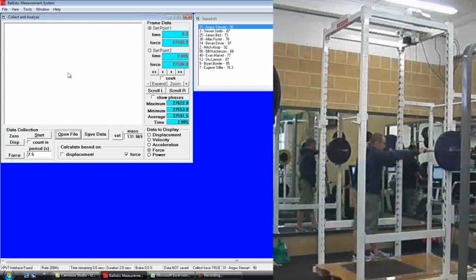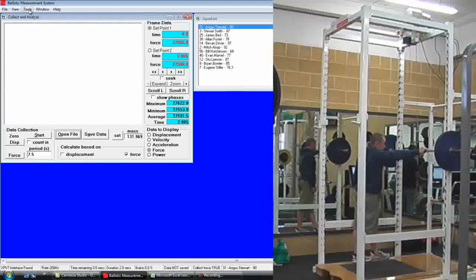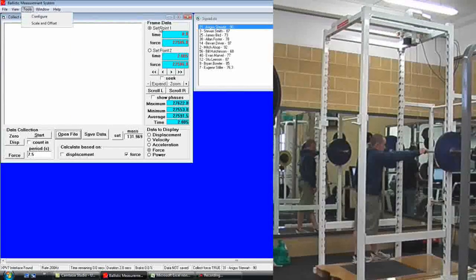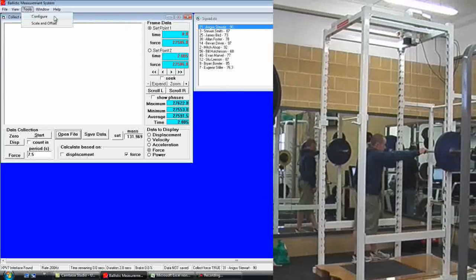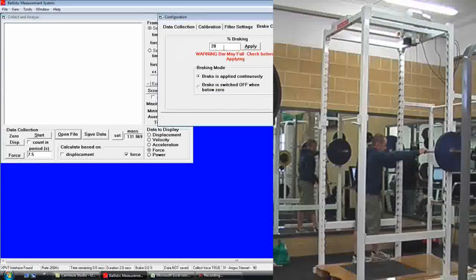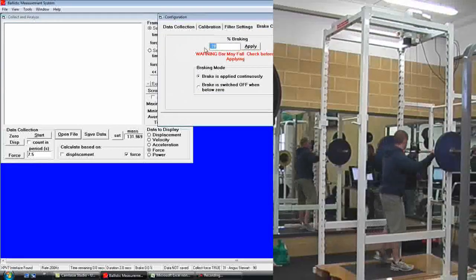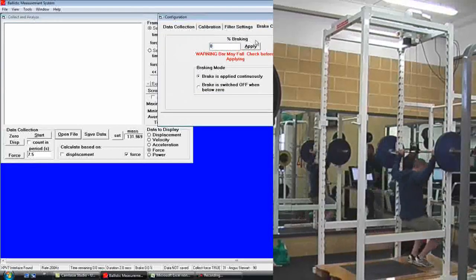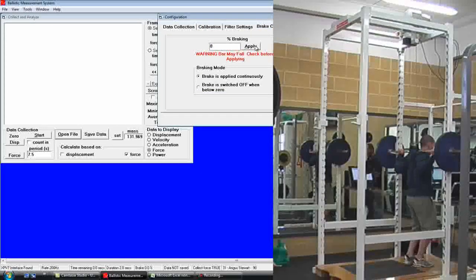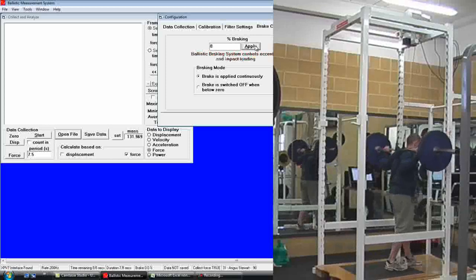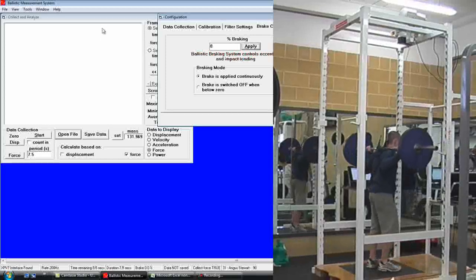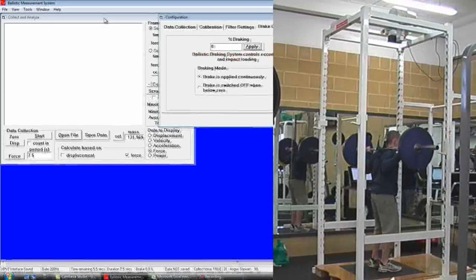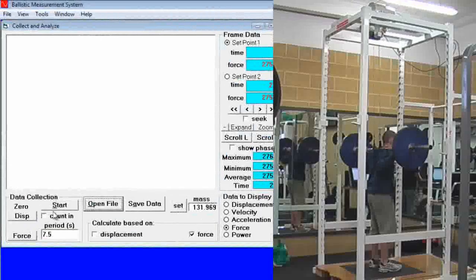We are then going to go to tools, configure, brake controller and set the brake controller to zero and apply. This means there is now no braking on the load.